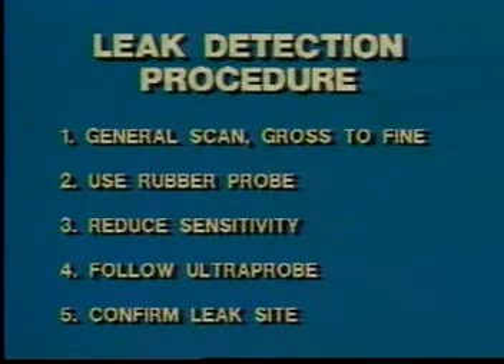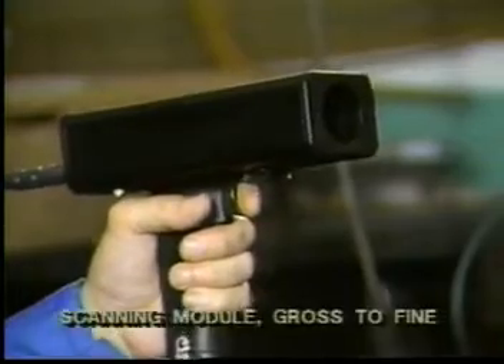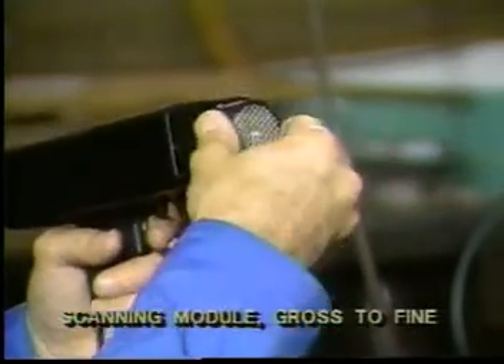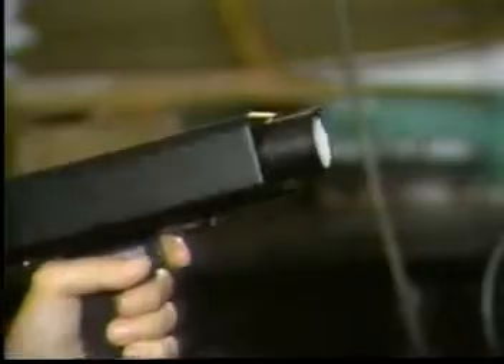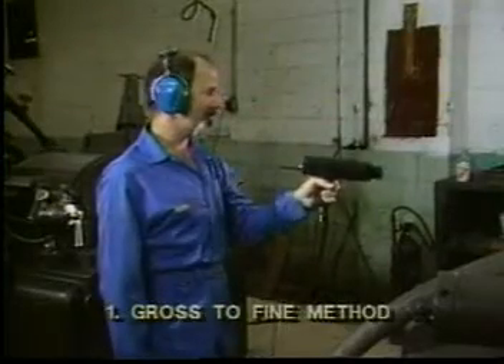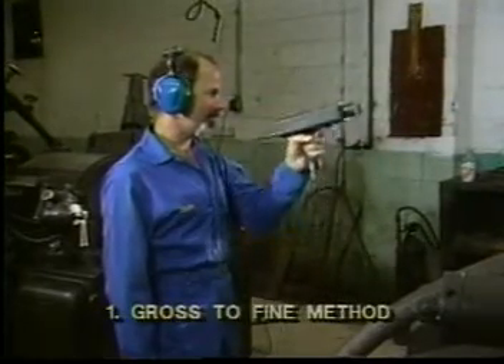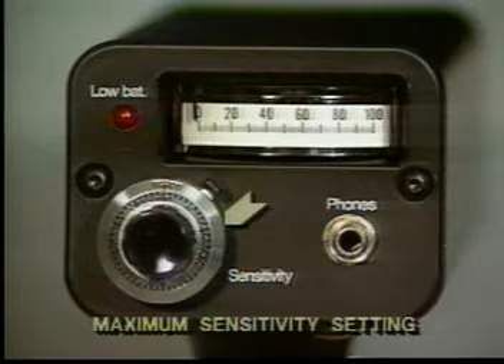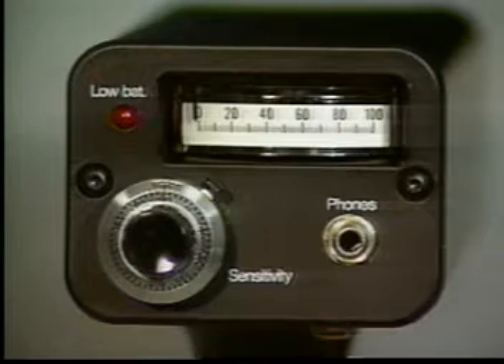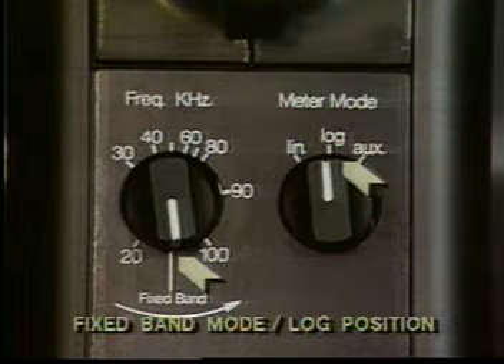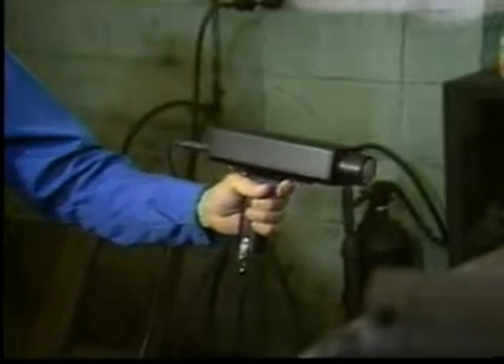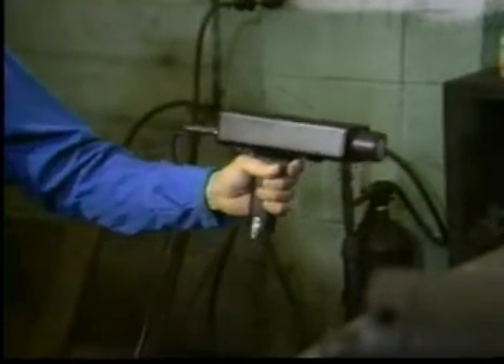Now we'll take a closer look at the leak detection procedure. First, using the ultraprobe scanning module, we will follow the intensity of the signal to get closer to the leak site. This is the first step in what we call the gross to fine method. To pick up gross signals, scan with the sensitivity level set for most situations at maximum and use the fixed band mode. The meter mode should be in the log position. Scan the area, closing in on the leak site by listening for its characteristic rushing sound.